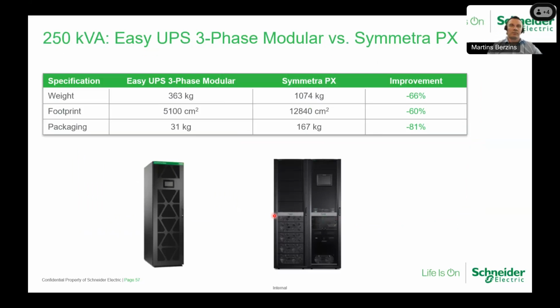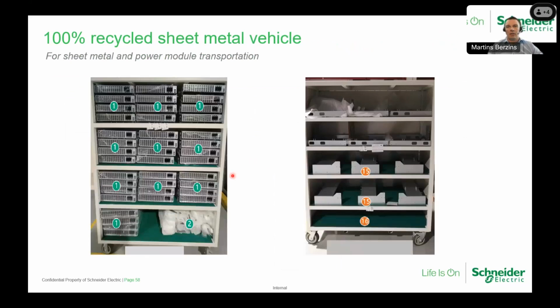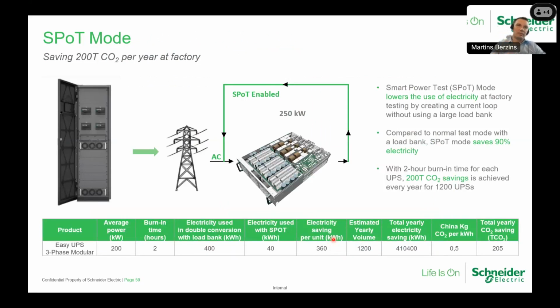So if we talk about the packaging, for example, if we compare the Easy UPS 3-phase modular to the existing Symmetra PX unit, on the packaging itself, we are saving 81%. And regarding the footprint and the weight, we are saving up to 60%. Even the small details are important. For example, for transportation of the power modules and metal sheets, even recycled sheet metal vehicles are used inside the factory.